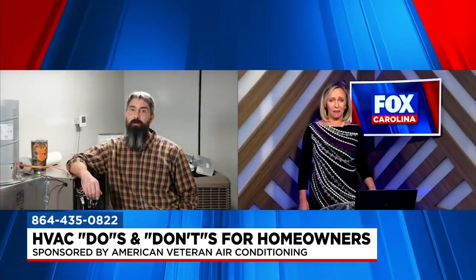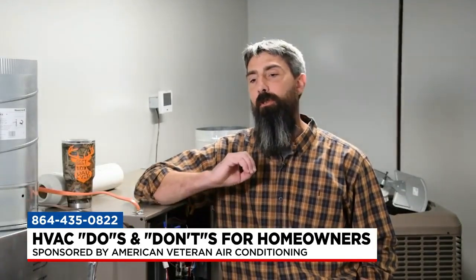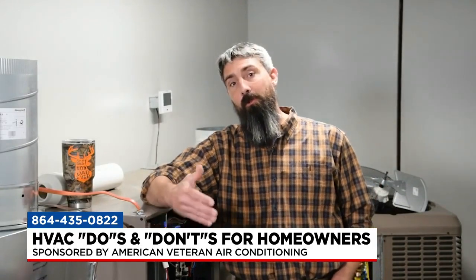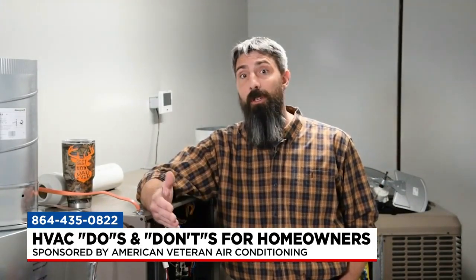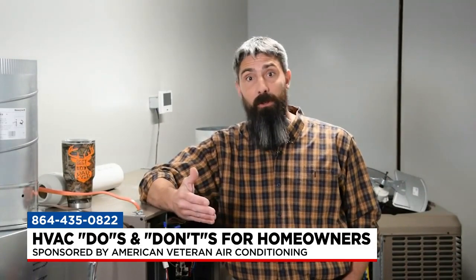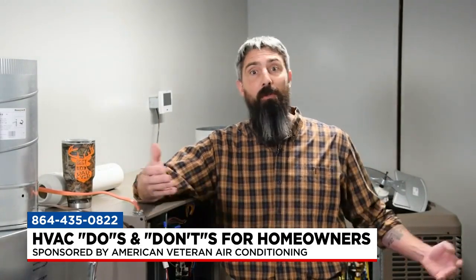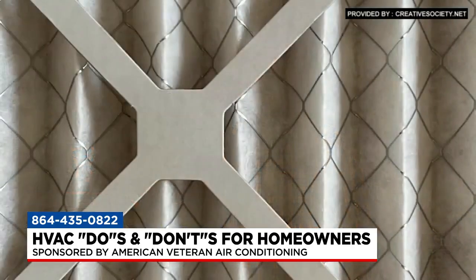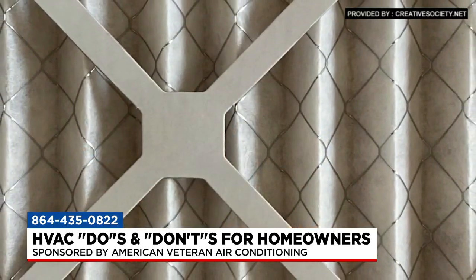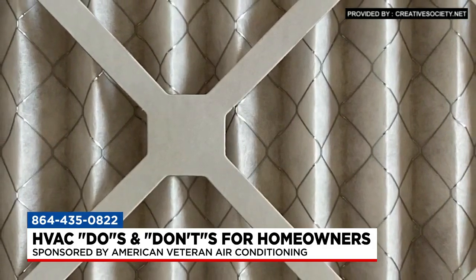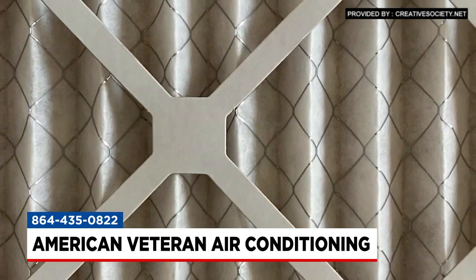And some homeowners get caught up in other things, they might forget about their filters. But that's a big one. You can't repeat that too often, can you? You're absolutely right, poor airflow causes the most degradation to a system than anything out there. It's the most common cause of failure that we come across. People ask us when to change the filter. Change it when it's dirty. In my house, that takes about 2 weeks, I've got 4 dogs running around. With other customers, it might be a month. MERV 8 or less is what I recommend on all air filters, nothing higher, because then you're purposely restricting airflow and causing more problems.